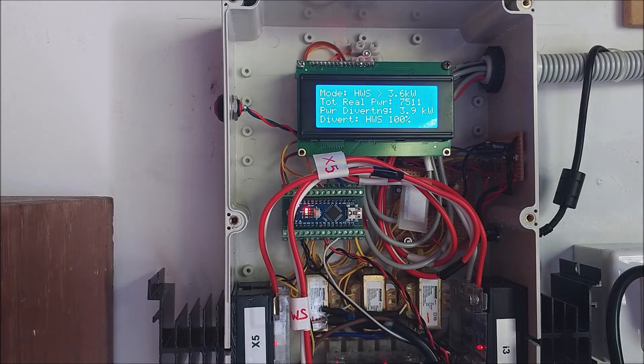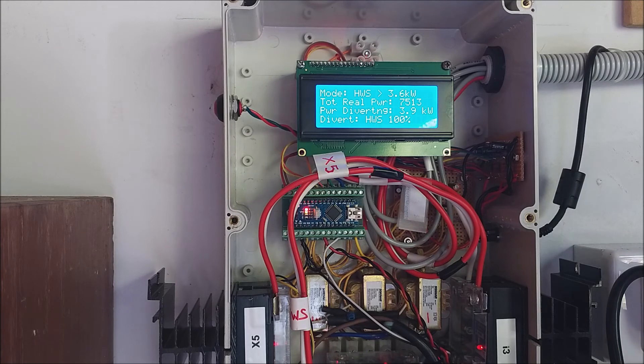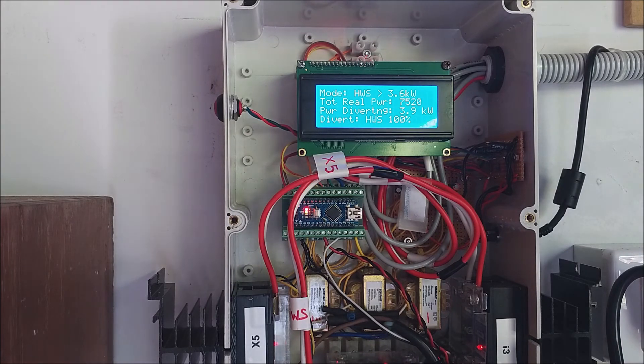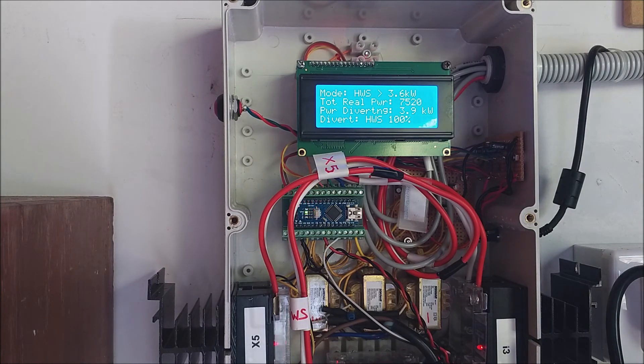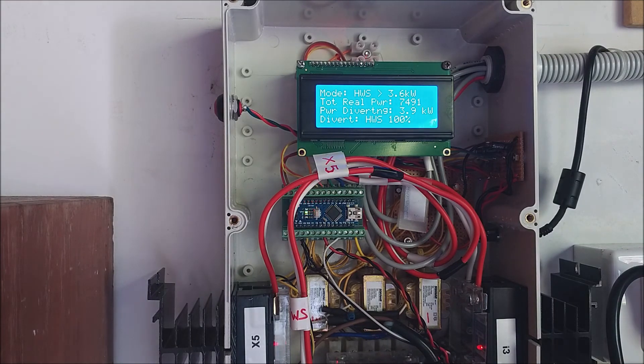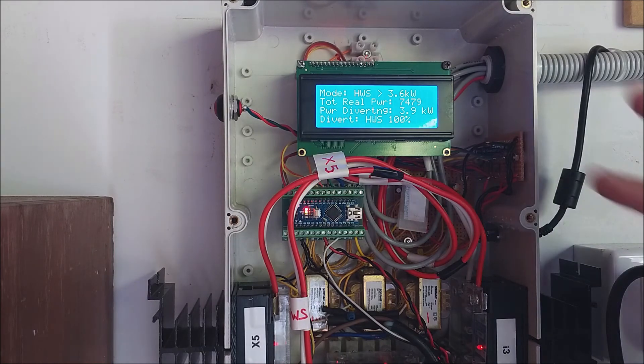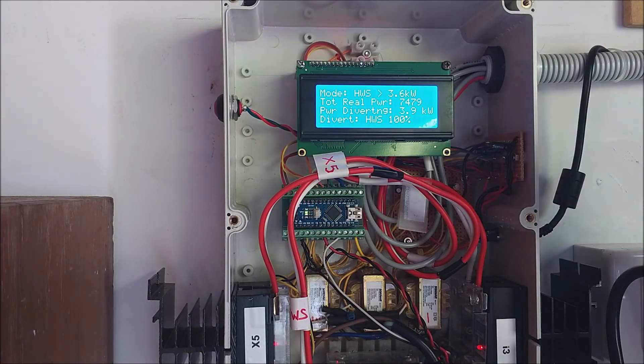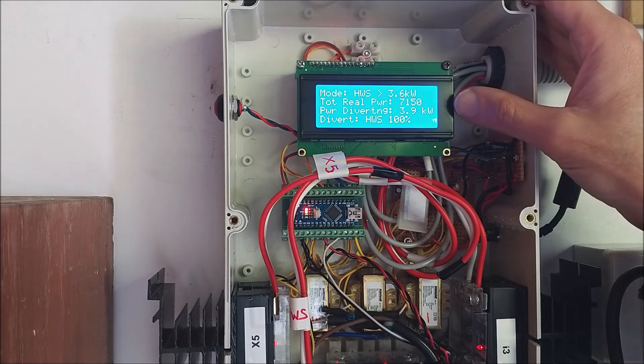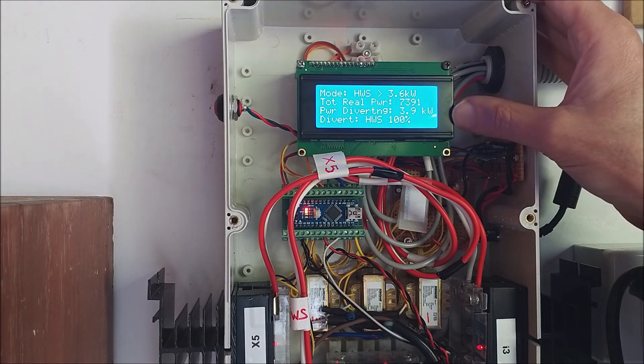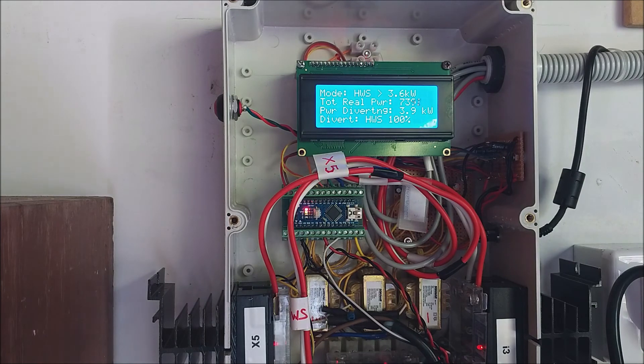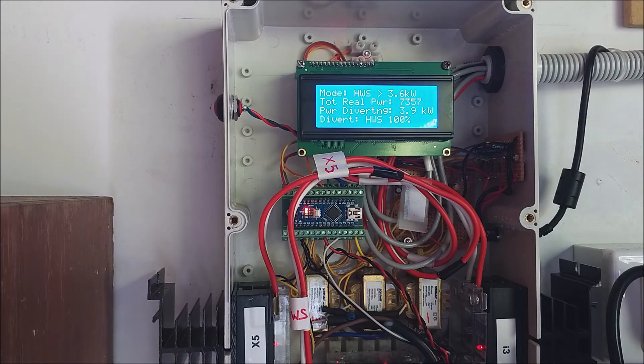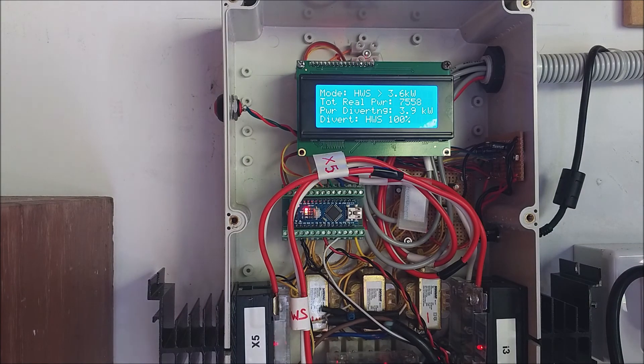This final mode is hot water service grid, the 3.6 kilowatts essentially then what we're looking at here is that we're looking to have a mode where we never draw from the grid to heat the hot water with the electrical power. So I have to be producing in excess of 3.6 or in my case 3.9 kilowatts to switch on the hot water service. So in this case it'll either be a hundred percent diversion or duty cycle or zero percent if I fall below and export at 3.9. At the moment it's quite sunny right now, we're getting 7 kilowatt export 7.4 kilowatt export and we're obviously maxing out on what we can divert to the hot water service right now. But once that figure drops below 3.9 it will switch the hot water off, so that's another nice approach or model if you don't want to draw anything from the grid to heat your hot water.